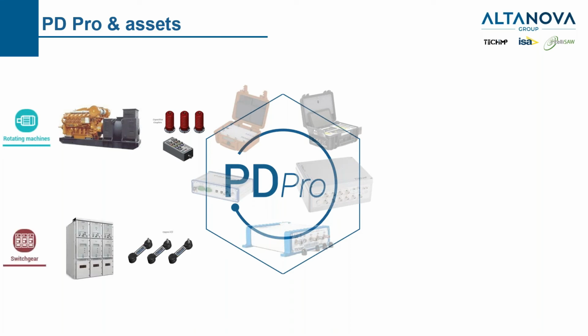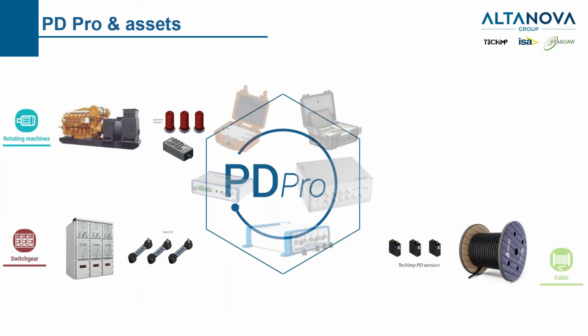Another asset we can test, for example, is air insulated switchgear. We can test them with TEV, with HFCT. All this information can be included in the data itself, and will always be with the data, like a permanent fingerprint on that one. And the same, we can obviously use the PD Pro for testing cables.